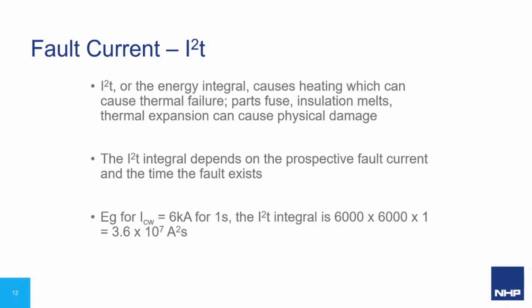By extrapolating the current and time values of our available fault, we arrive at our energy integral. For example, if we have a specified 6 kA fault for 1 second, the energy integral would be 3.6 times 10 to the 7. We can also do this for the equipment in our assembly to see what level of energy it can handle without damage. Mathematically, we need to ensure that the energy integral of all the equipment we select for our assembly exceeds the energy integral available from the fault at that point of the installation.